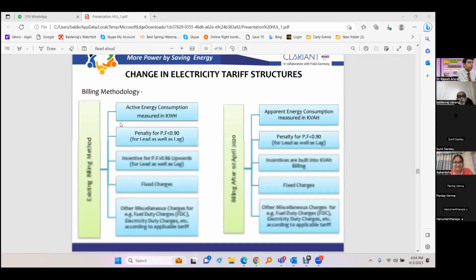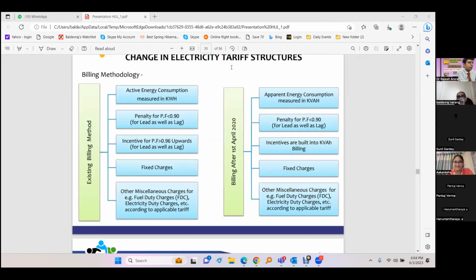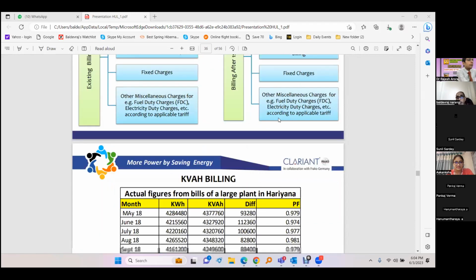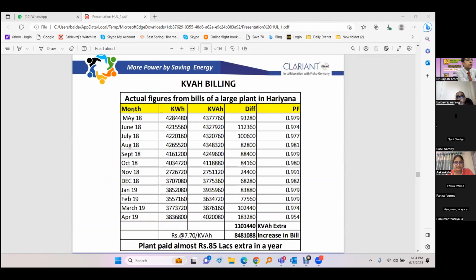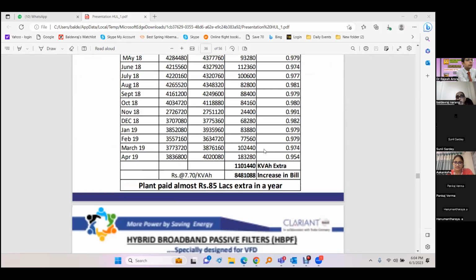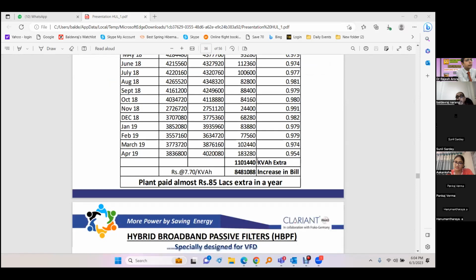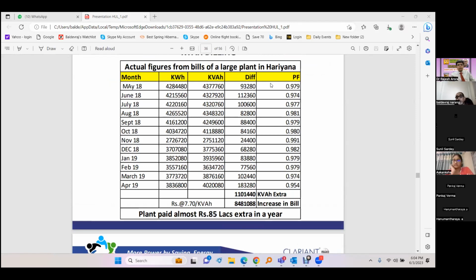So this is another slide which shows the difference when kVAh billing and kWh billing was there, and there is a diagram shown here. If the power factor is maintained close to almost unity all the time in all the 12 months, still the difference is very substantial. Over a period of 1 year, these people had to pay about 11 lakhs extra because the power factor was not maintained close to unity. This is normal. It cannot always be zero difference, but we can always go close to unity.